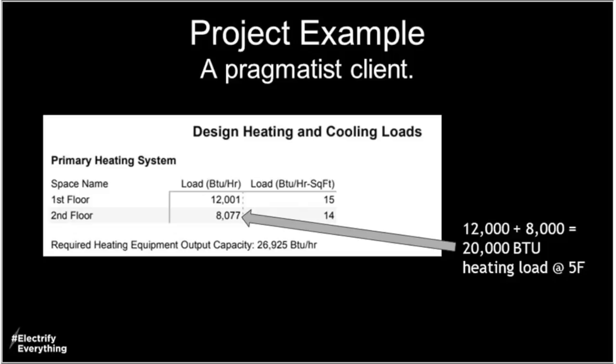So I had to have a conversation with Paul because there's no furnace that will heat this house evenly. And you want to be able to match how much heating and cooling that house needs as much of the year as possible. So the smallest standard furnace you can buy is 40,000 BTUs. And if you want to go lower, you actually have to buy a modulating 60,000 BTU furnace, which will dip down to about 20,000.